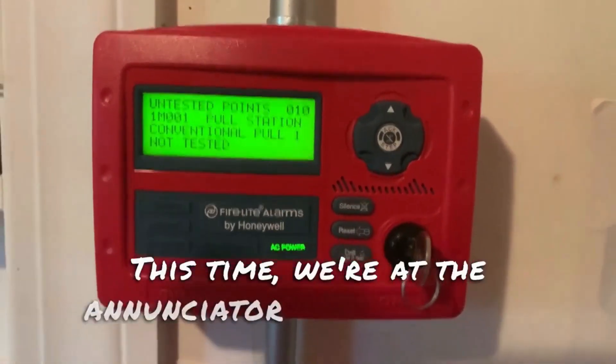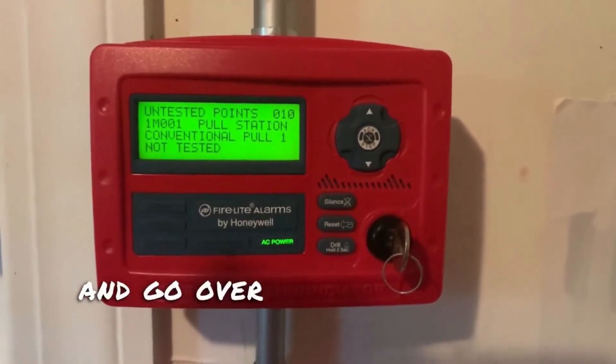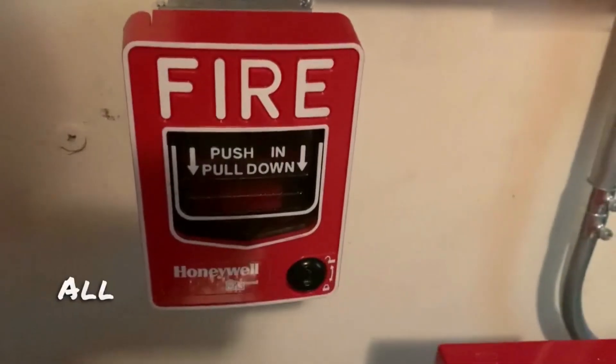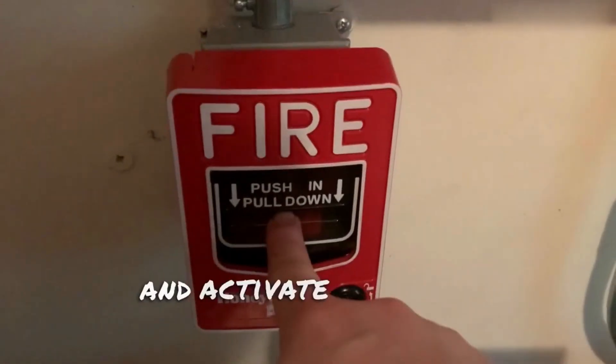Alright, this time we're at the annunciator instead of the panel. Now we're just going to go ahead and go over beside the panel. We're going to test the first conventional pull station. Alright, now we're going to go ahead and activate the first conventional pull station. Here we go — in three, two, one.